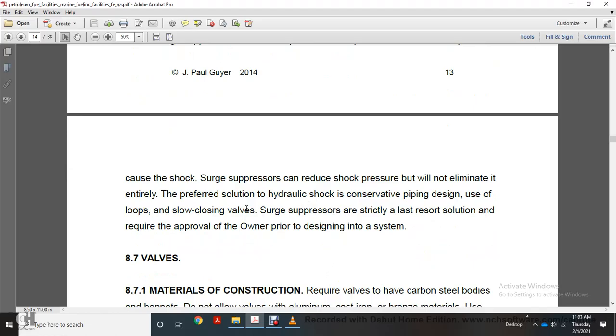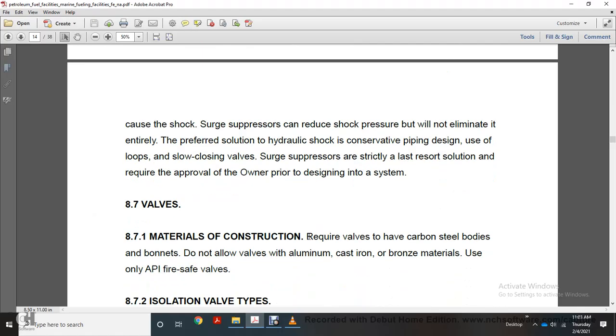Use loops and slow closing valves. Surge suppressors are strictly the last resort solution. Require approval of the owner prior to designing one into the system.